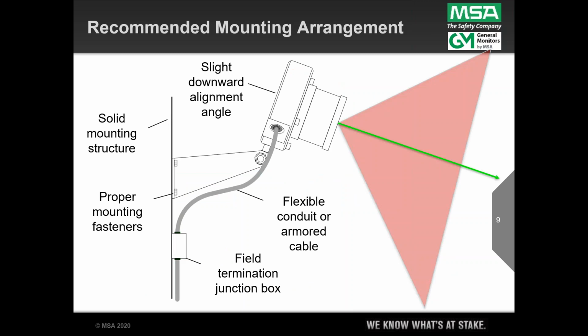As far as mounting, from left to right, as an ex-field guy, I like to see a solid mounting structure, right? These detectors, both the multi-spectrum and the UVIR, the IR sides use modulation or flicker as part of their signal processing requirement or algorithm, and that's because hydrocarbon fires breathe, and you can really see it with your kerosene, your diesel fuels, your crude oil fires, where that flame actually breathes, and it comes up and makes a big cloud, then it releases, and that's like a 5 hertz flicker on those heavy liquid fuels. But even methane or propane have a flicker rate as well.